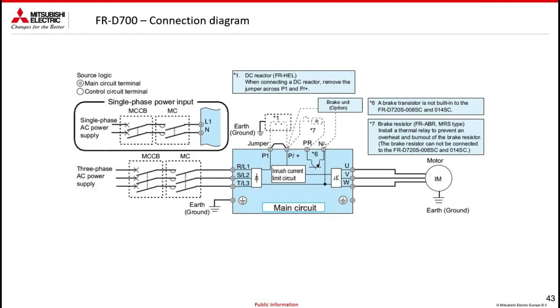The connection diagram shown in this slide concerns the power section. L1, L2 and L3 for three-phase power, rather than L1 and L2 for single-phase power. Between P1 and P/+, you can mount a DC inductance, obviously by removing the jumper. The harmonic content is proportional to the size of the inverter itself. The inductance must be mounted on inverters larger than 75 kW. An external braking resistor can be mounted between P/+ and PR to dissipate energy. U, V, and W are the motor output.